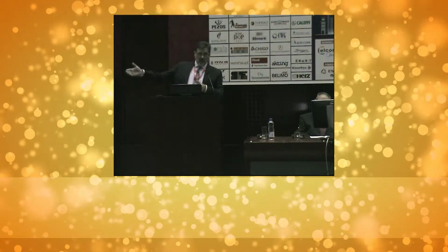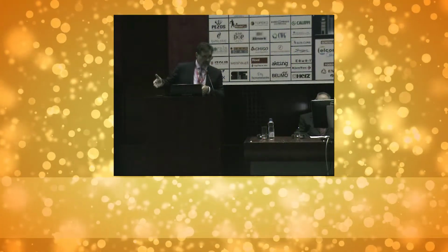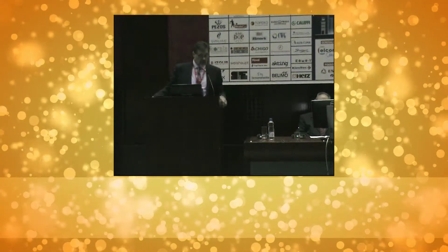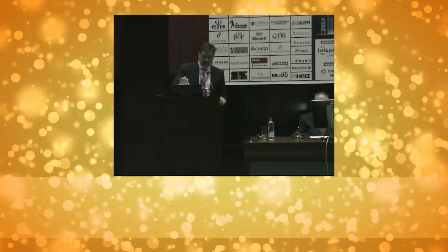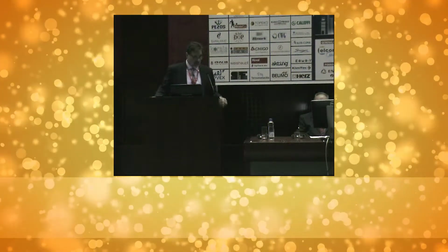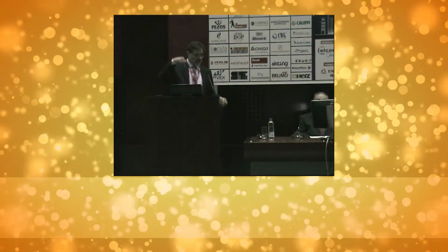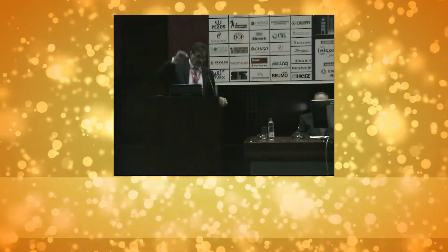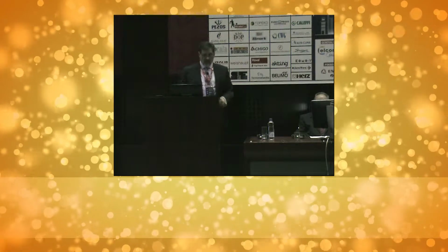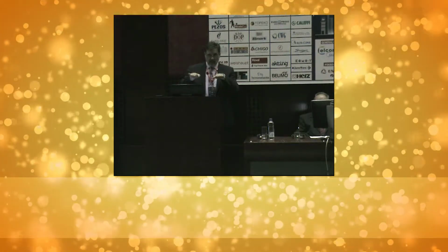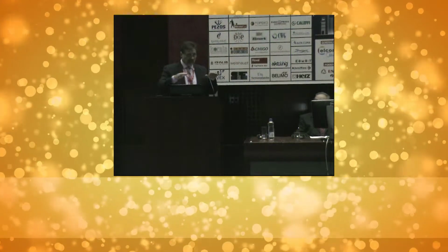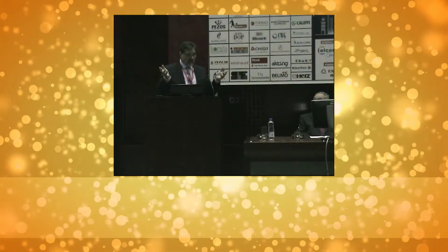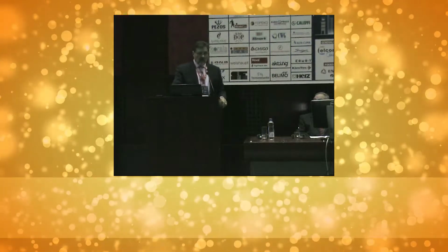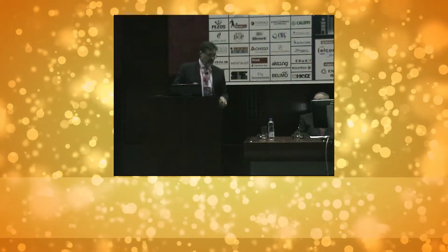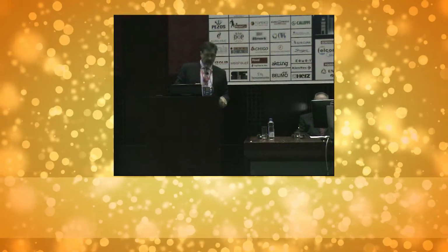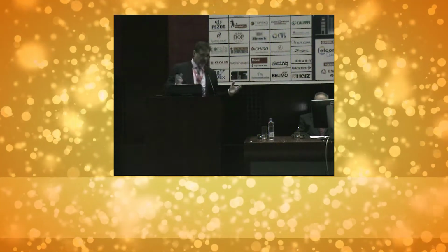The proper way would be 5 straight diameters in the front and 3 on the back, which would cost more, so people kind of agree that, hey, this is the proper way of dealing with this. Also, we experimented with how this sensor has to be positioned. Is it the horizontal or vertical position, depending on the damper? We established it has to be in the same plane. Basically, we just created a tunnel and looked at the performance of the air, how that does. This way, we guarantee that this sensor will go to 100 feet per minute very accurately, and about 5% on and off, which is pretty good.